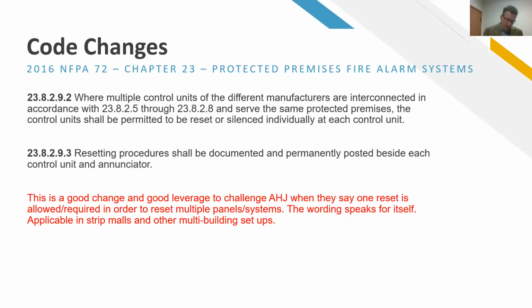But the code does protect us and say, yes, it is okay to have multiple points of reset. So that's just the takeaway from this section here. And my advice to anyone who's managed a building: try to have one fire alarm system in one address. There are certainly code provisions that allow other applications. A lot of times you'll see this in a single level situation where you have, like, a medical clinic next to a bunch of big box retail stores, right? So that's sometimes where you'll see a separate panel in kind of one structure.